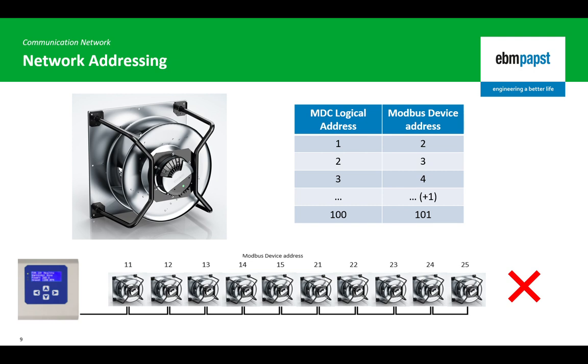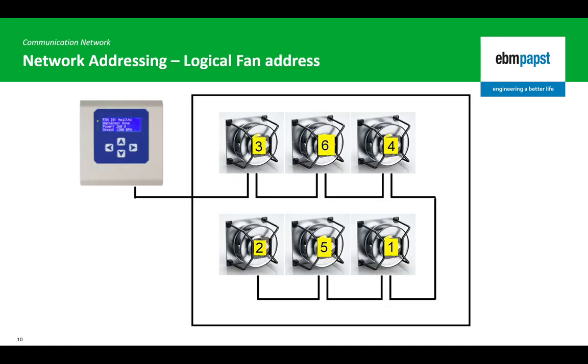Secondly, if the client requires a logical order between the fan position and the fan number referenced on the display of the MDC controller, the logical addresses and the Modbus device addresses can be manipulated. In most cases, the OEM manufacturer of the array will not take care that the fans in the array are positioned in a logical sequence of ascending serial numbers. This may result in the fan address shown on the display of the MDC not reflecting its physical position in the array.